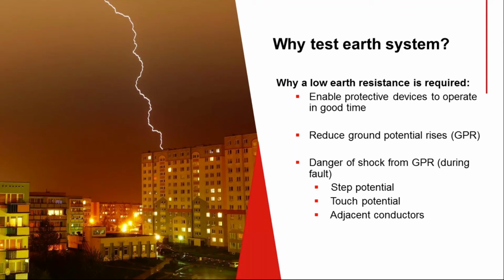Ground potential rises. We'll talk about them as we go along, and then we'll take a look at things like step potential, touch potential, and some other factors of that nature. Figuring ground potential rise. In other words, you don't want voltage rise anywhere in your building across your equipment or across personnel, and that's what you're trying to eliminate.